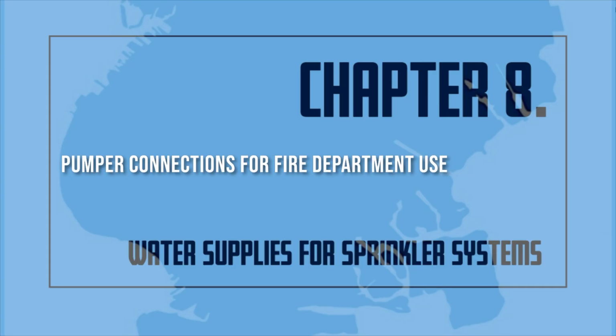Local Law 58/2009 requires color coding of fire standpipe and fire sprinkler systems to have the risers, cross connections to the water supply piping painted red. The fire department connection to a combined standpipe/sprinkler system shall be painted yellow. Fire department connections must always be accessible.